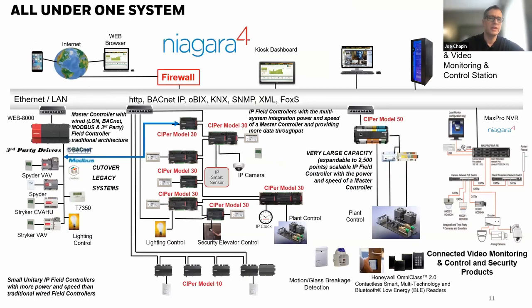is what the slide was just previously when it's connected to the IT-based network, ring configuration. The blue jagged line on the left-hand side that jogs over, what that's showing you is with these controllers, not only can I connect to the IT network, the high-speed computer network, I also have I/O modules that can bring in your BACnet, your Modbus. What does that mean? I can cut over legacy systems without placing new cable if I don't need to.